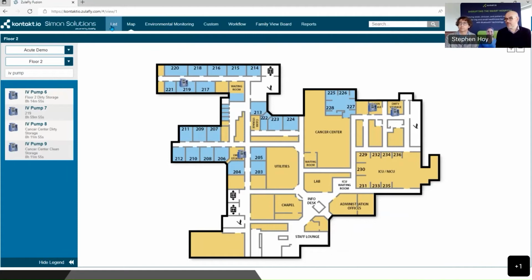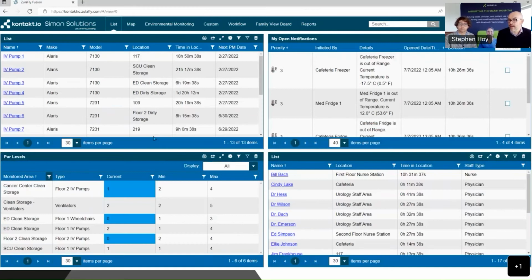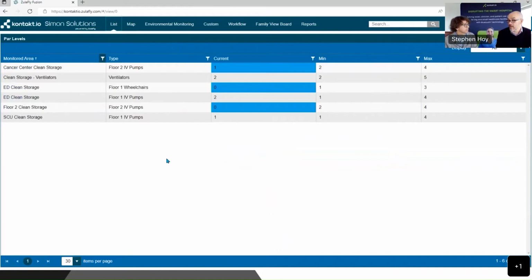Health board or an acute trust, there could be many thousands of devices they need to keep track of at all times. How can we get to that place where if you're the head of medical engineering, all of the assets you're responsible for are held in the solution and trackable by the solution? Yeah, well, ultimately this is really down to the strength of the Bluetooth low energy network. So if we have a Wi-Fi network with Bluetooth capability, then we're away. But remember, we also have the migration service, so it allows us to put it over Wi-Fi. So if there's any sort of Wi-Fi, we can also plug in the gaps using the migration service.